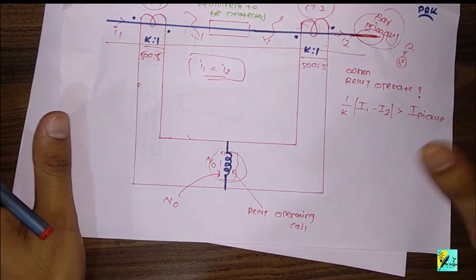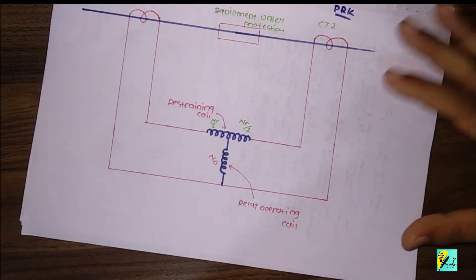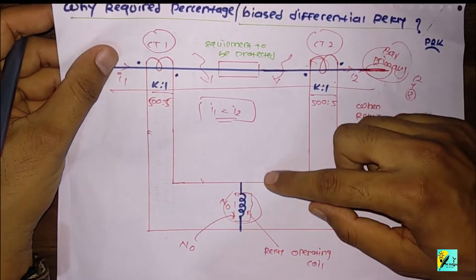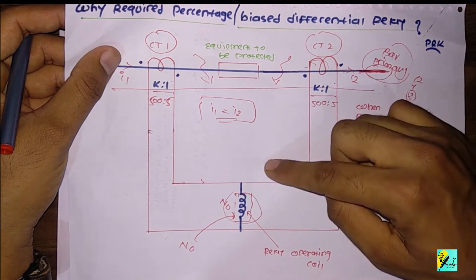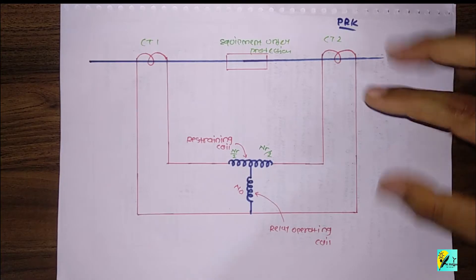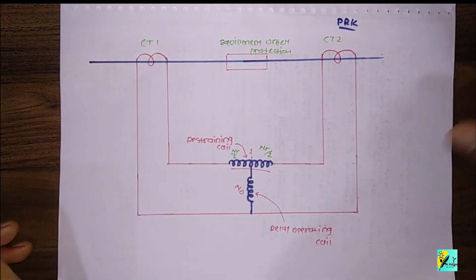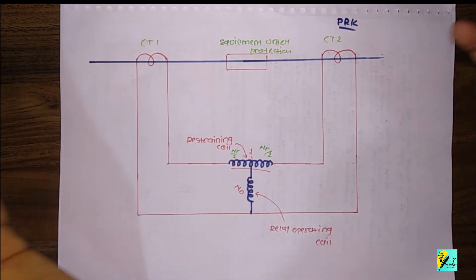That is why we need to improve this particular section. So we replace the simple differential section with a restraining coil. This is the simplest structure of the differential relay — it contains only the operating coil. But in the improved structure, this additional coil is called the restraining coil, which will produce a force or torque that opposes the operating coil of the relay.